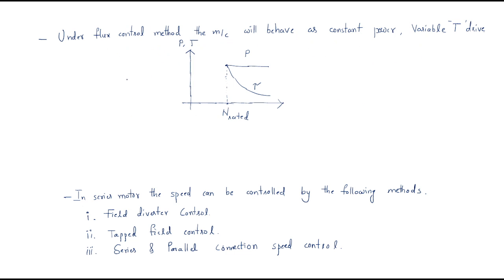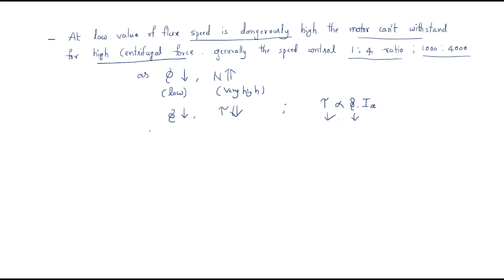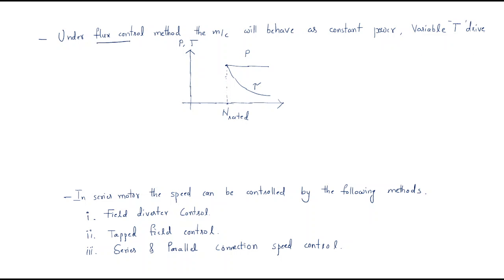Considering power: when flux decreases, speed increases and torque decreases. Both changes compensate together so power becomes constant. Under the flux control method, the machine behaves as a constant power and variable torque drive. On a speed versus power and torque graph — since this is above rated speed — power is constant and torque decreases with increasing speed.